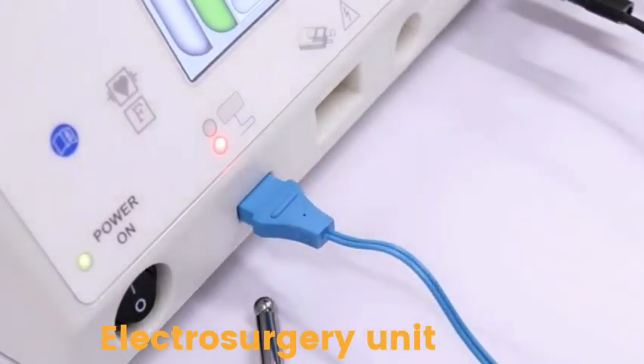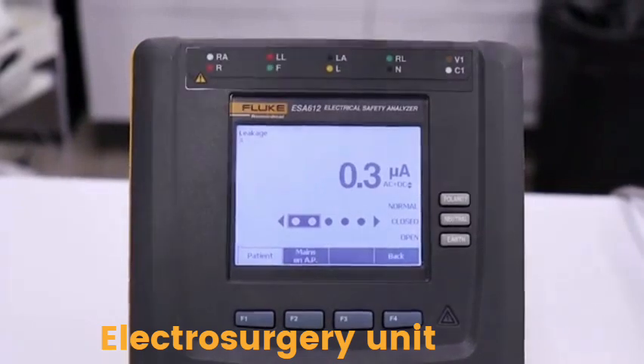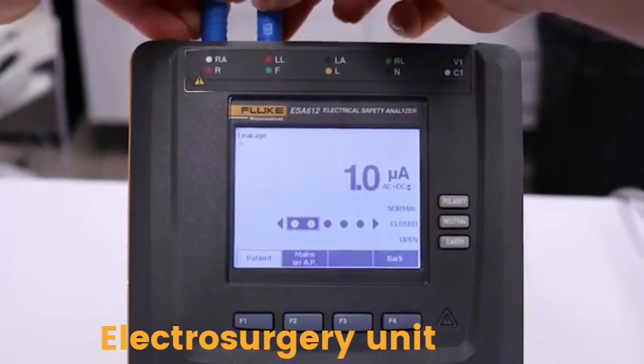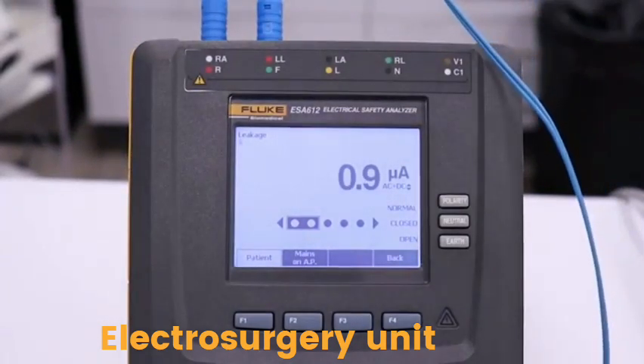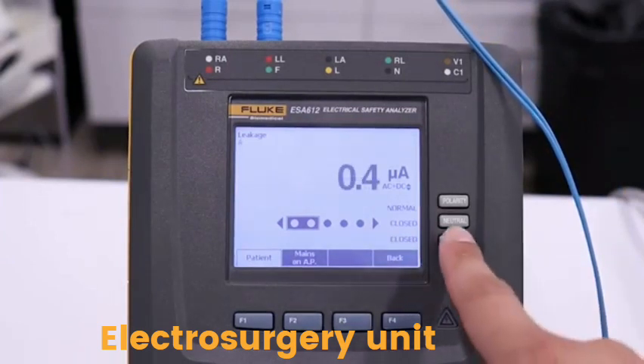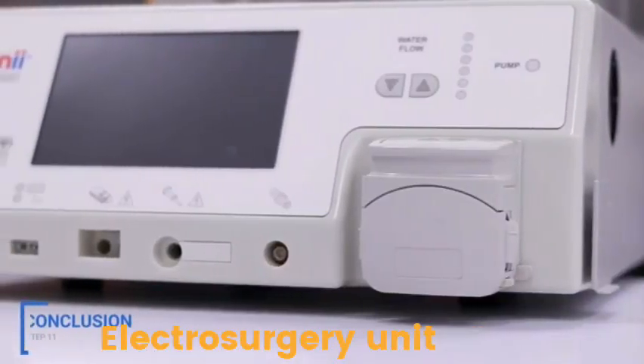Plug the opposite end of the neutral test leads into the first two receptacles on top of the ESA. Test for normal polarity, closed neutral condition, and single fault open earth condition. At this point, the video has come to a conclusion.